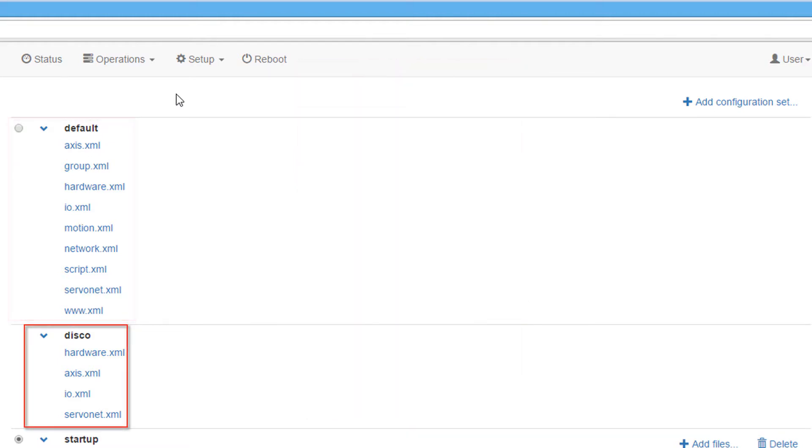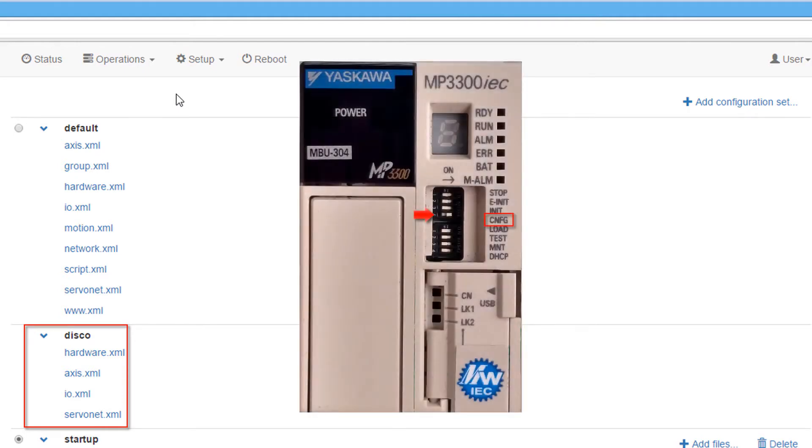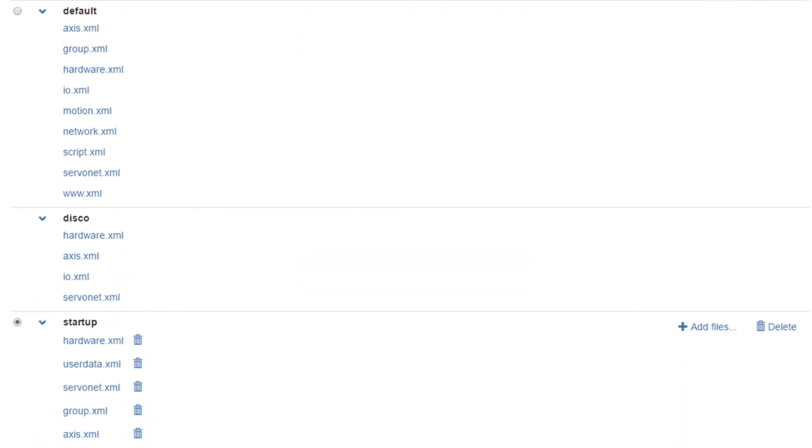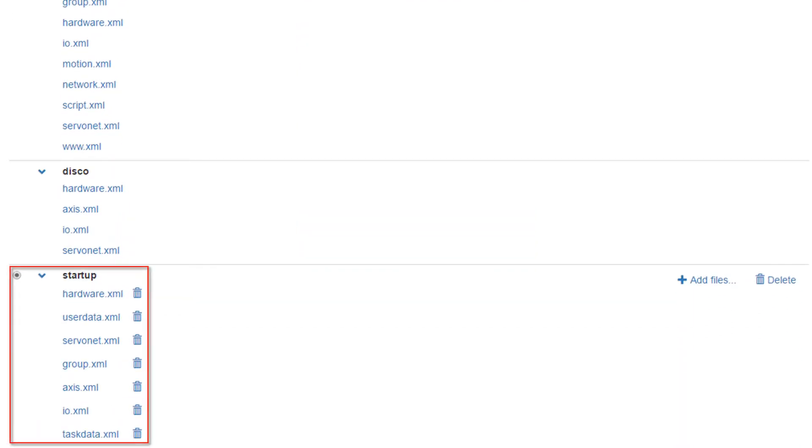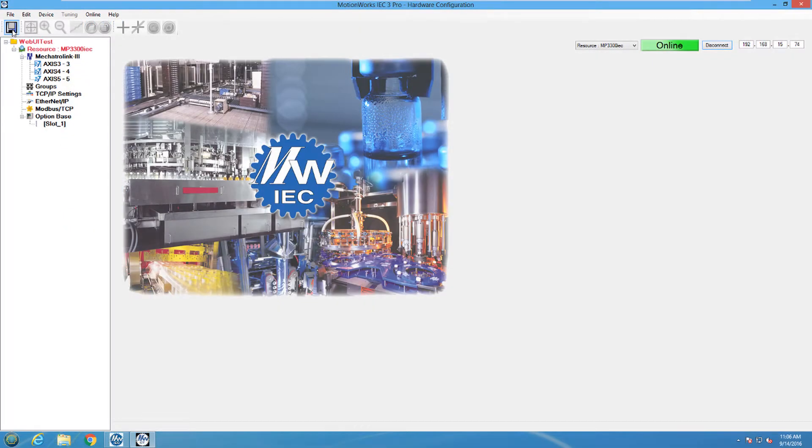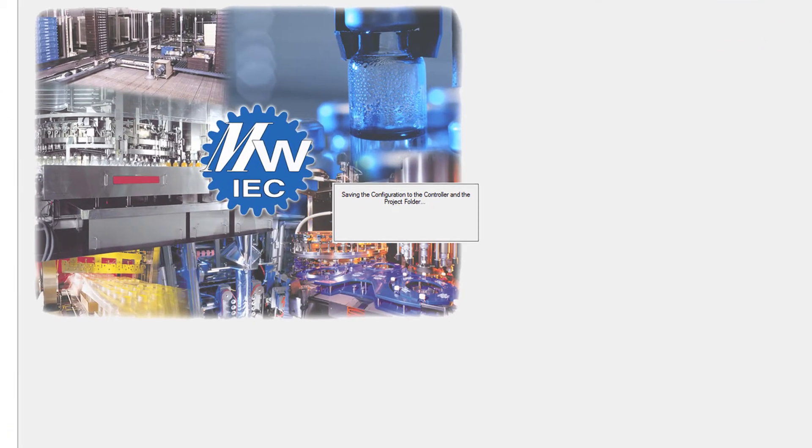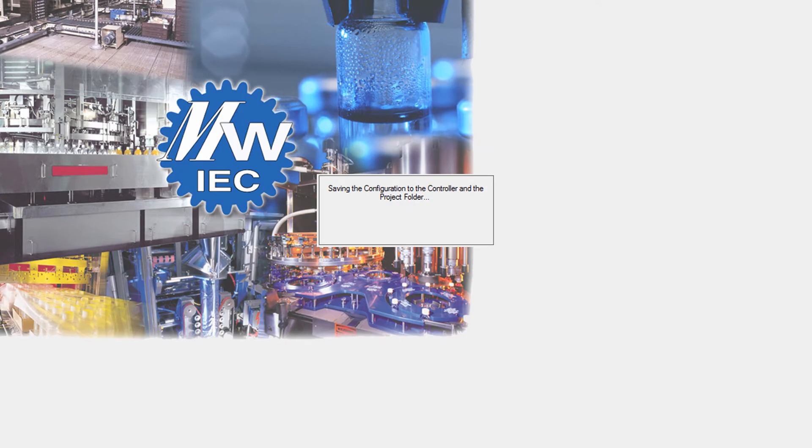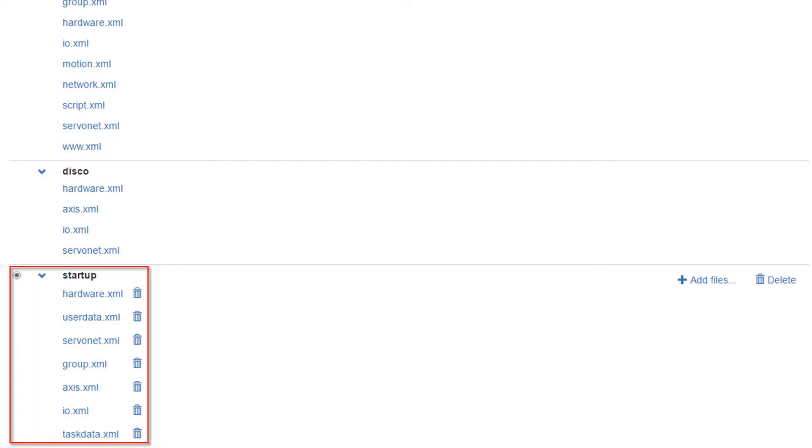The disco configuration is used when the config switch is set on the controller, and when there is no startup configuration. This configuration updates upon reboot to find new hardware that is attached to the controller. The startup configuration is created when the hardware configuration is saved in MotionWorks IEC. It is not recommended to view or delete the startup configuration files.